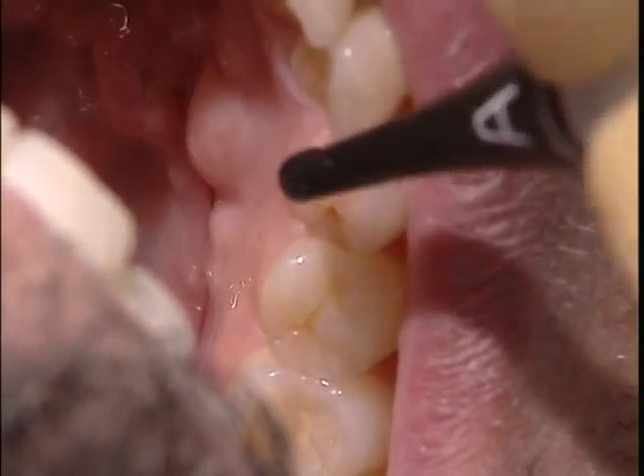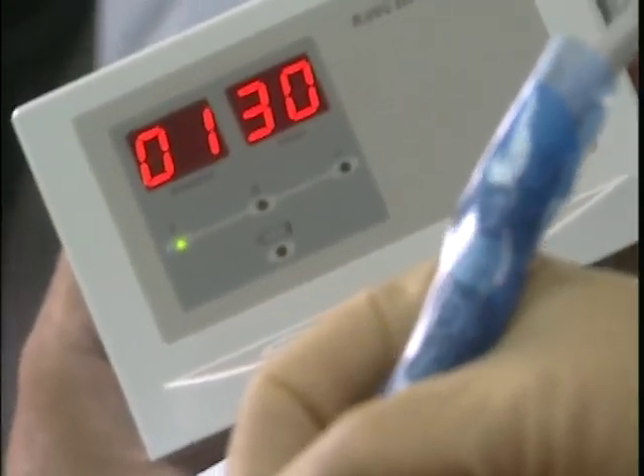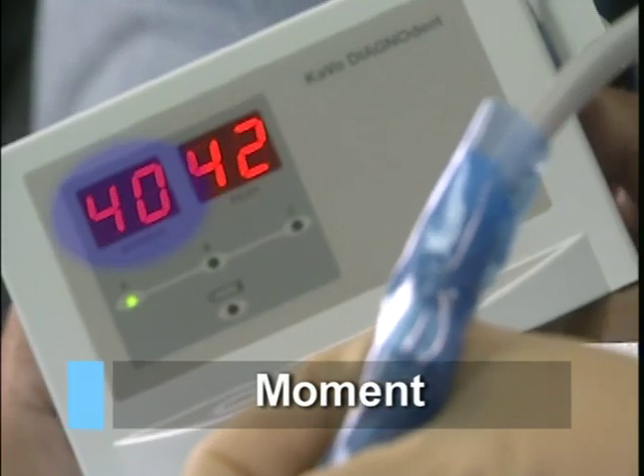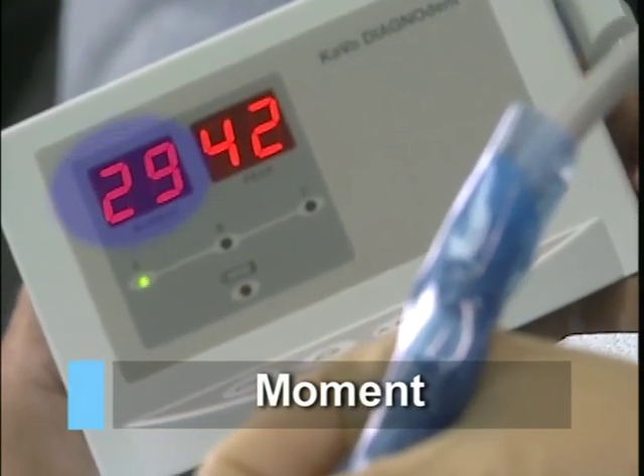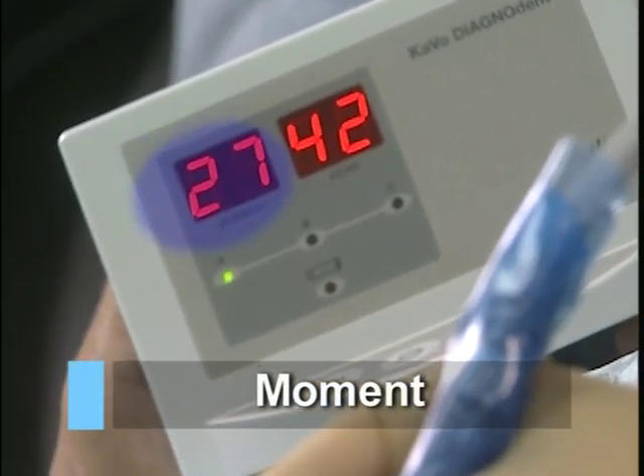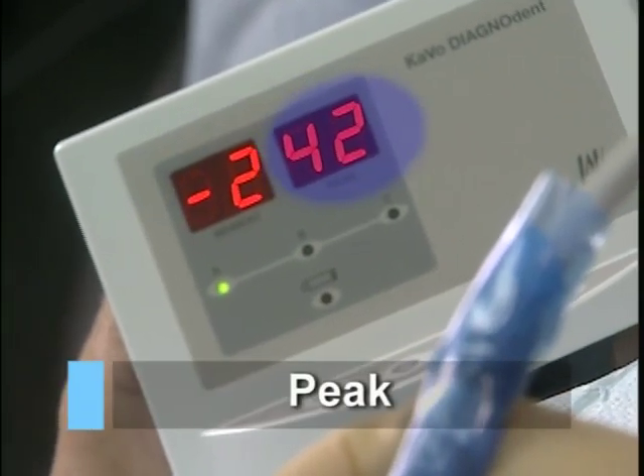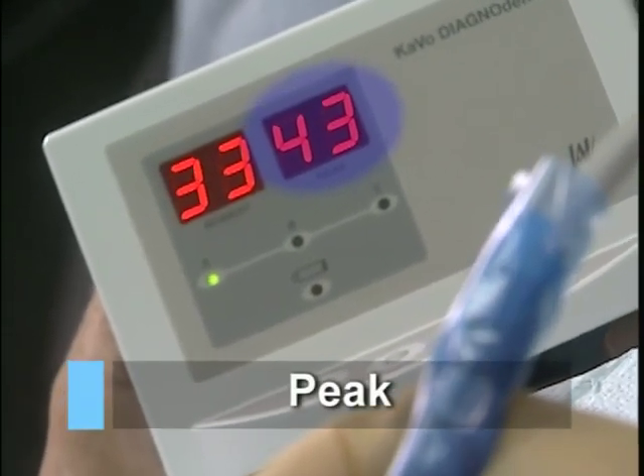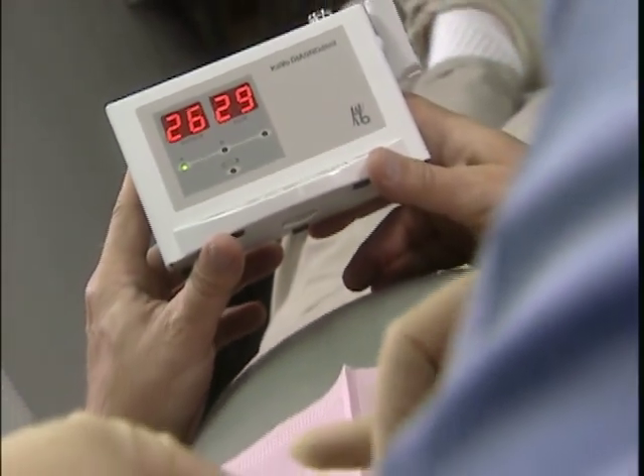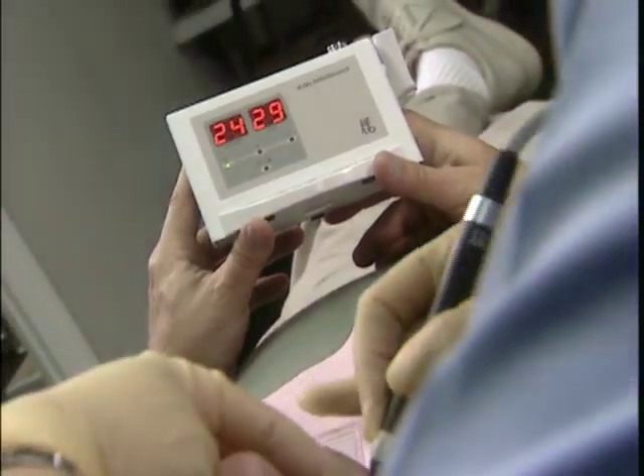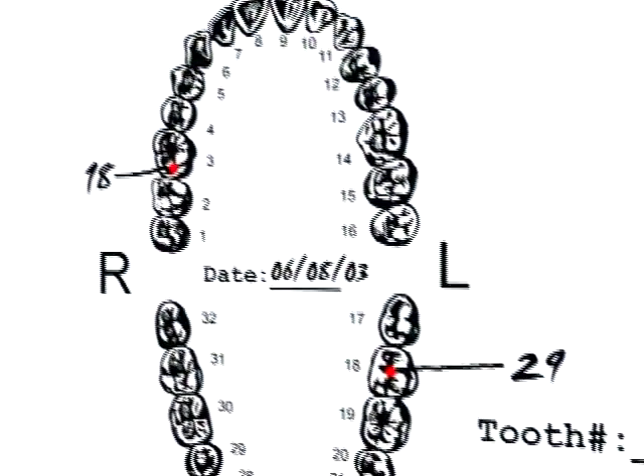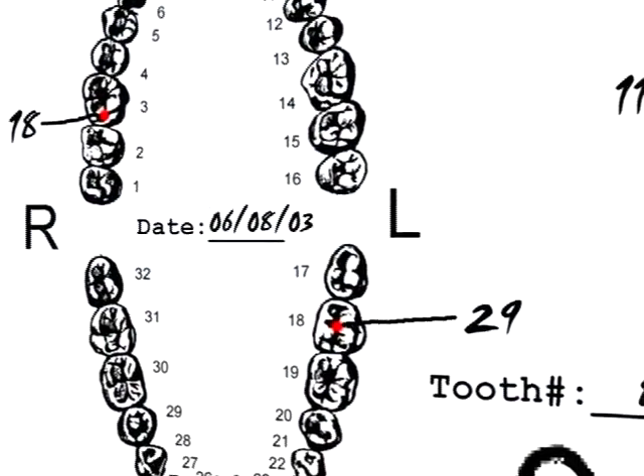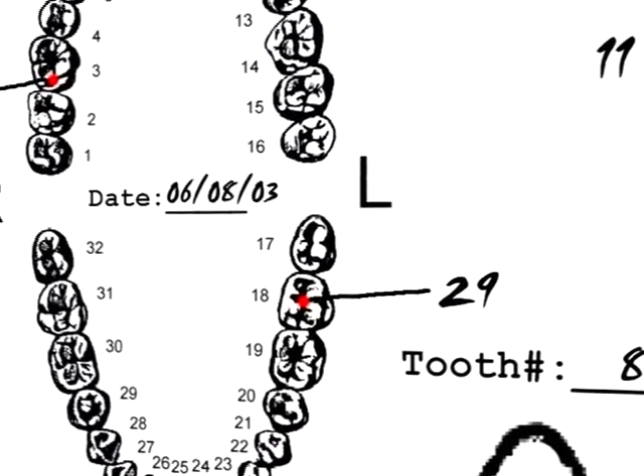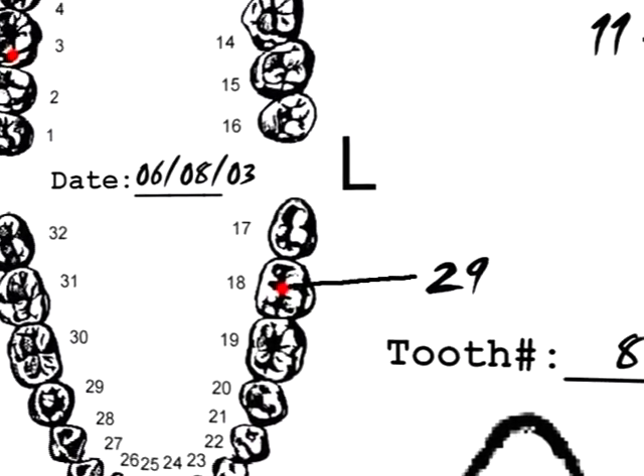Two values are indicated on the DIAGNodent: moment and peak. The moment display indicates the real-time value the probe is measuring. This value changes as the probe tip moves. The peak display captures the maximum value measured in a sequence. Significant peak values and their respective locations should be recorded in the patient's chart to compare with future exams and to verify actions to third-party carriers.